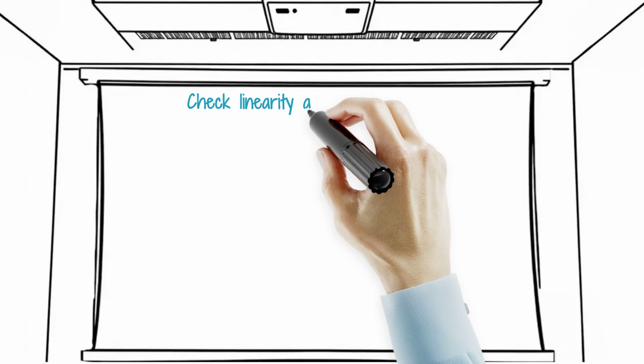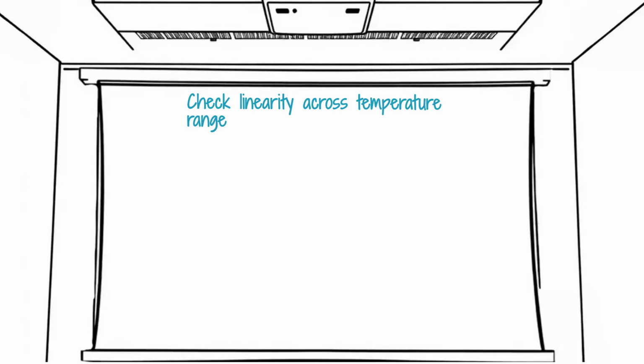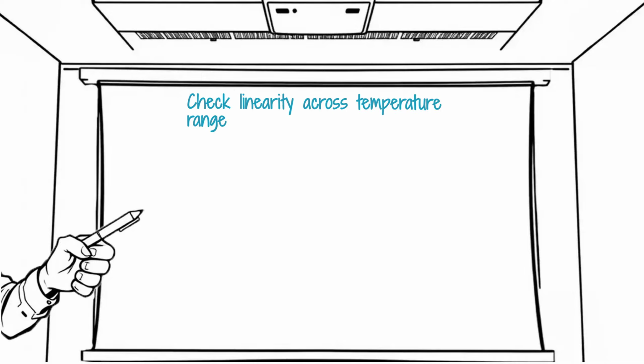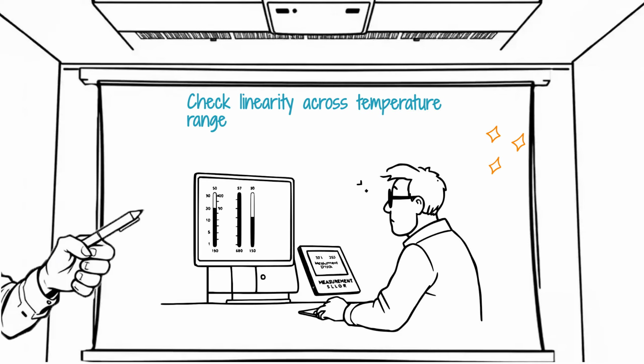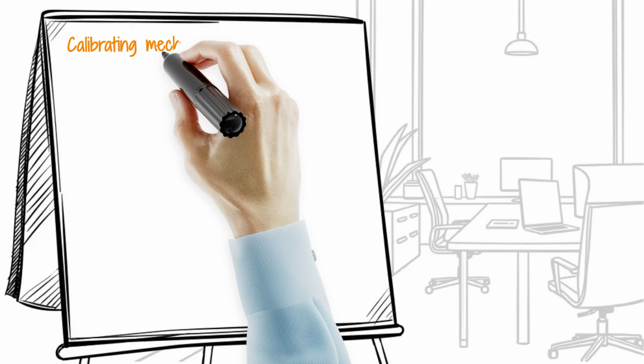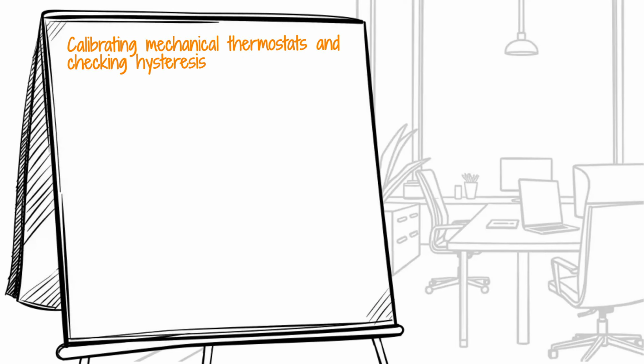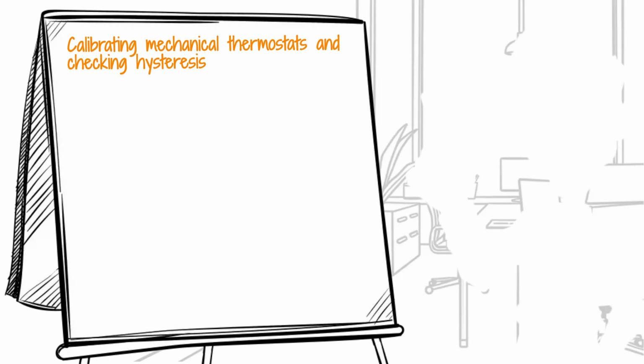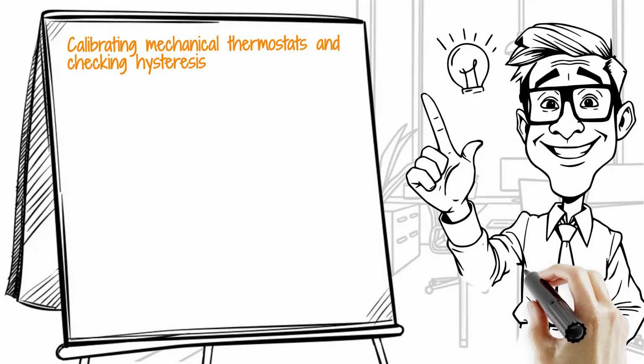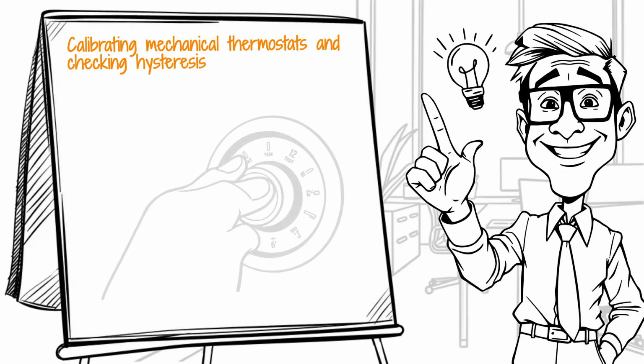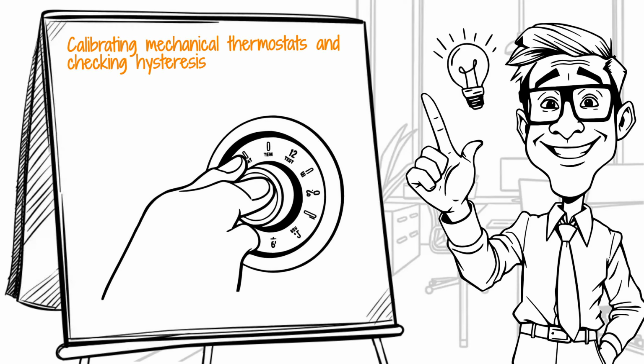Move the heat source to the midpoint and then to the maximum operating temperature to check for linearity throughout the scale. A sensor that is accurate at low temperatures but deviates at high levels indicates a loss of sensitivity and should be replaced. When calibrating mechanical thermostats for fans or heaters, manually adjust the set point dial until the internal switch clicks and verify this against the reference temperature. Check for hysteresis, which is the difference between the set point and the reset point, to ensure the equipment does not cycle too rapidly.